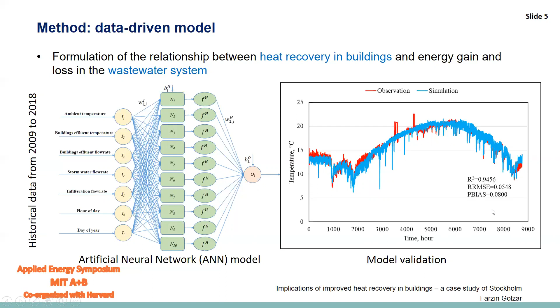For the purpose of considering local heat recovery, we considered heat exchangers as a passive local heat recovery technology, suitable for preheating cold water. The amount of wastewater temperature drop in the heat exchanger depends on different parameters, such as the physical properties of the heat exchanger and the temperatures and flow rates of the wastewater and cold water entering it.